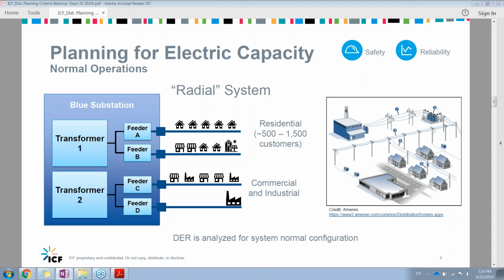When DER is analyzed, this is typically the configuration that's done during an interconnection study, and the DER may or may not be included in some of the abnormal configurations that we will look at in the next slides. So this system intact situation is sometimes referred to as N-0, meaning this is the normal system. There aren't any components that are out. Next slide, please.